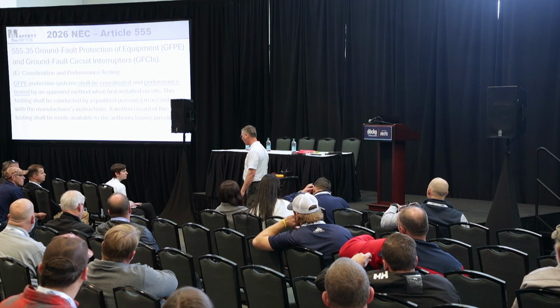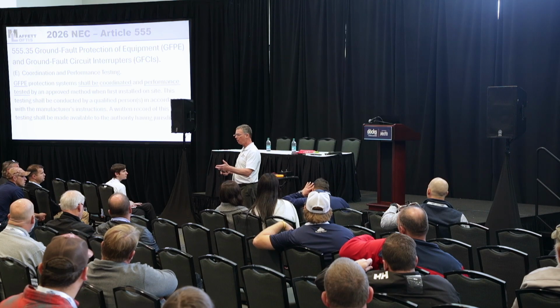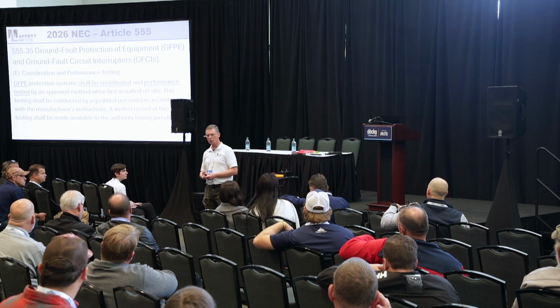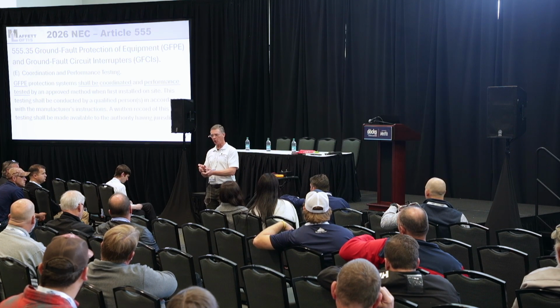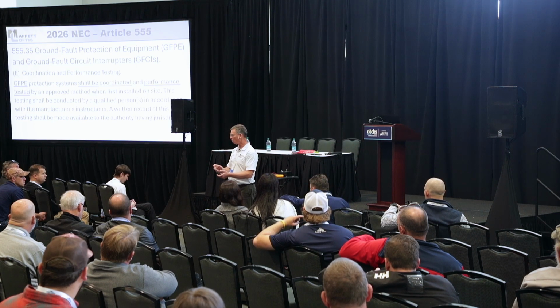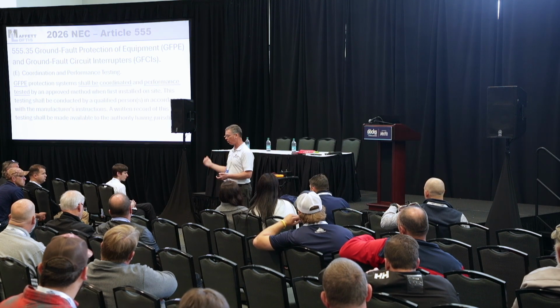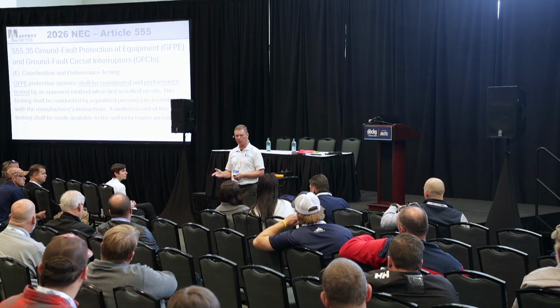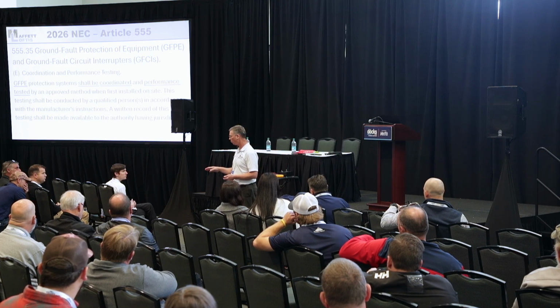I go through with 50 amp, 30 amp, every GFPE point I will test. I'll ramp the leakage current up to see where it trips and make sure it trips between my specified time and the code. I also test the timings of all those 30 milliamps and see how fast or slow it is throughout the entire marina.